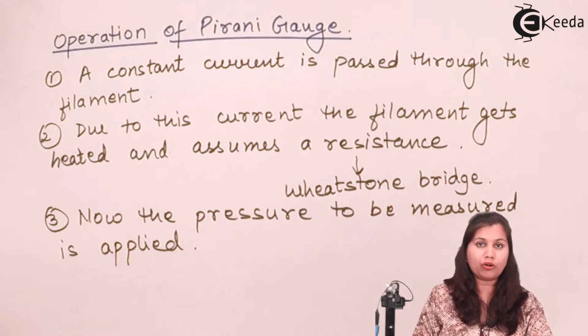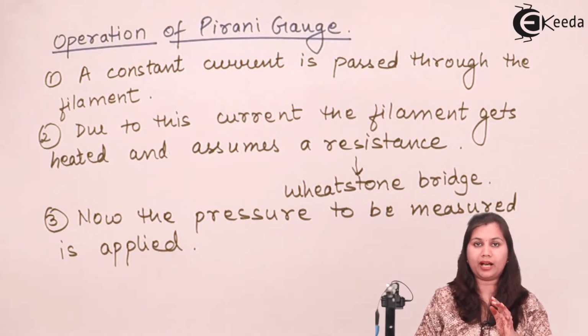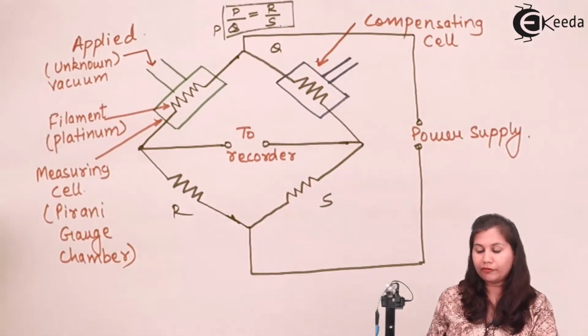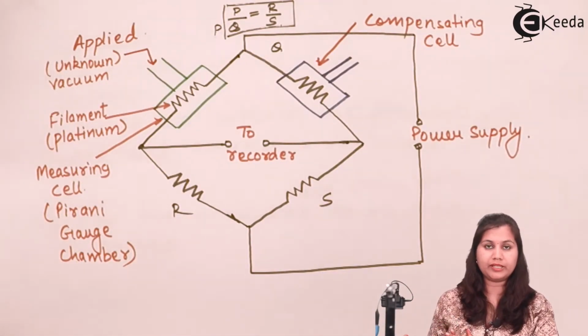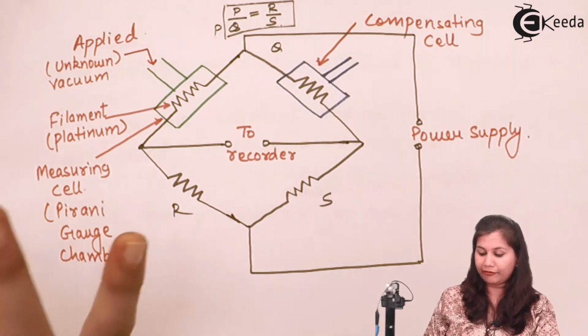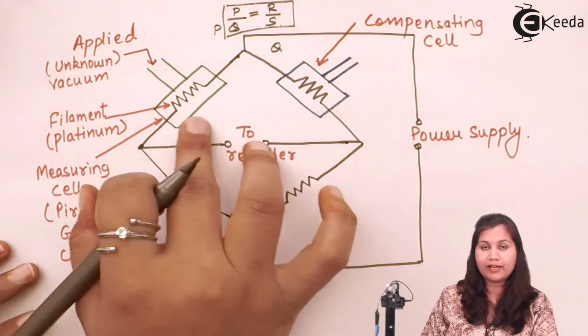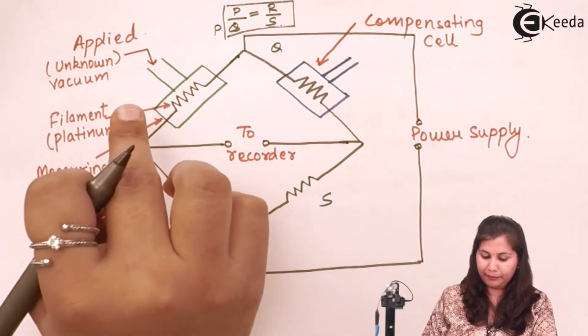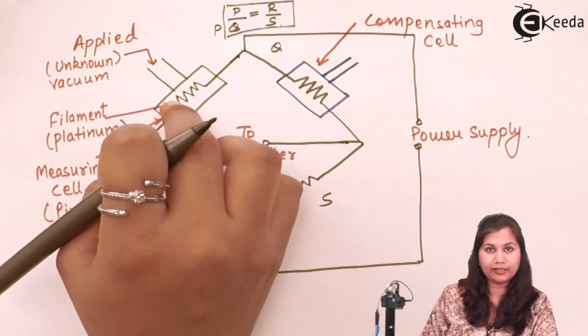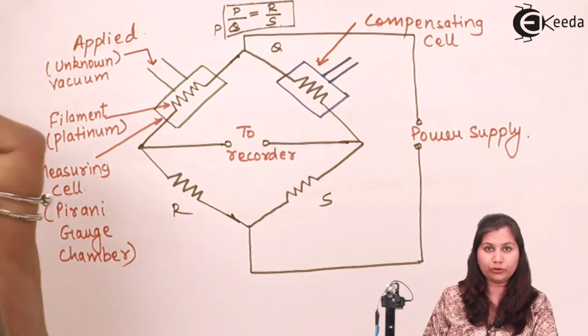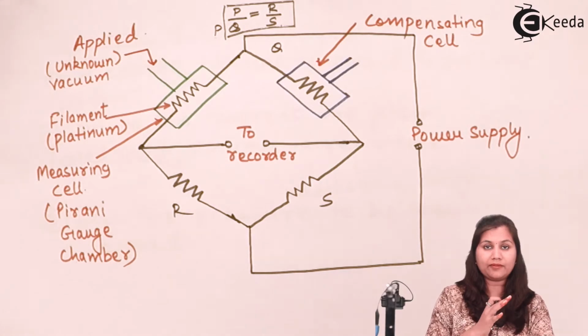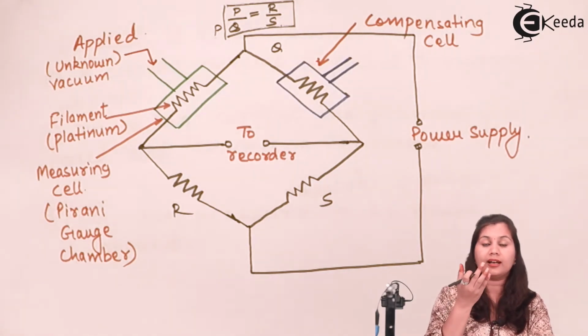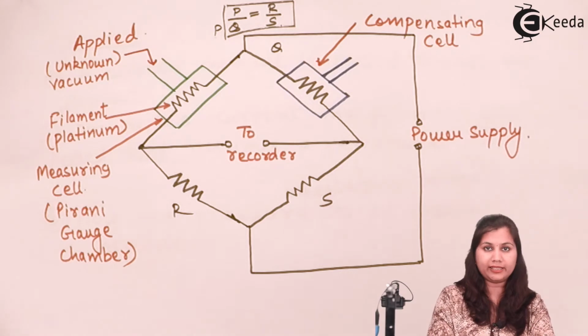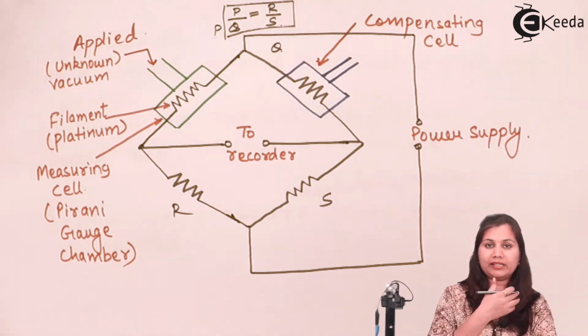Now the pressure which we want to measure is applied to the Pirani gauge chamber. First, we have measured the resistance by using the Wheatstone bridge. After that, we have applied pressure on this filament which is present in the Pirani gauge chamber. Now, due to the pressure which is applied, the density of the surrounding medium is going to change, because earlier in the principle we saw that the conductivity depends upon the density of the surrounding media, and density means the pressure.